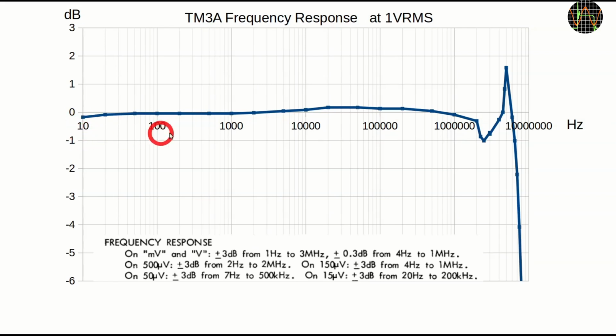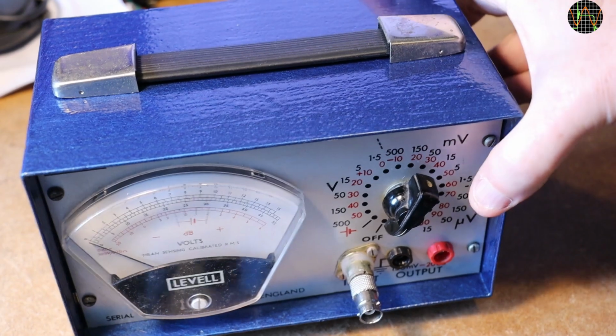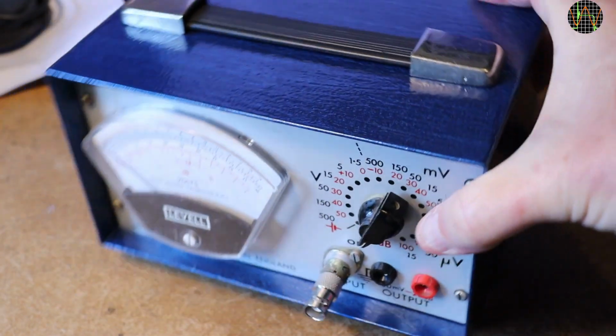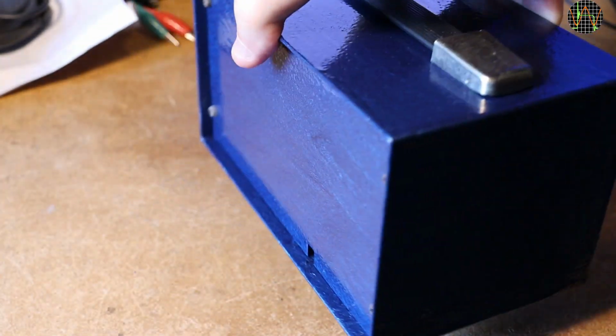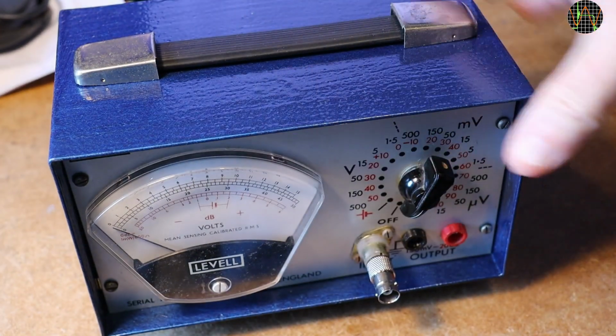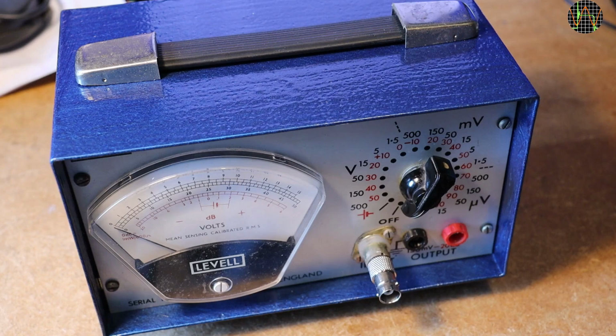Up to 1 MHz it should be within plus minus 0.3 dB, and the worst part here is plus 0.2 dB, so also well in spec. I must say I'm quite impressed by the TM3A. It delivers very good results with a fairly simple design. If you are on the lookout for an inexpensive microvolt AC meter, the TM3A or B are worth a look.